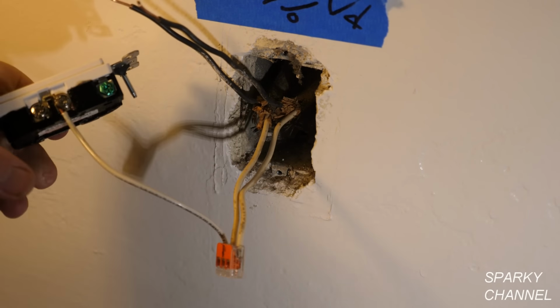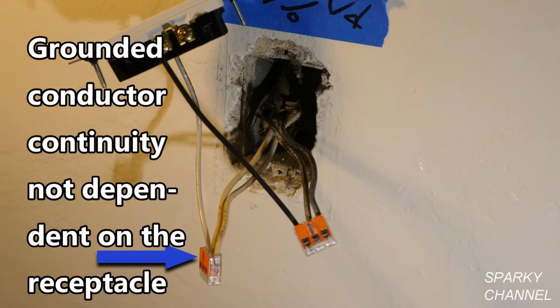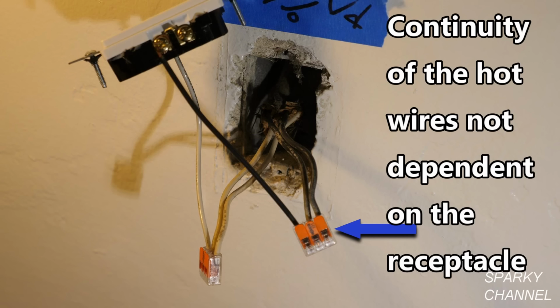Okay, so then I'm going to take the black hot conductor, prepare a pigtail, put that right in there, and I'm going to take that and go around either one of these terminals. It doesn't matter, they're hooked together. Tighten it down securely. Here you can see that the continuity of the neutral wires does not depend on the receptacle. If mechanical damage were to occur to the receptacle, electricity would still flow through the neutral wires back to the main panel. And because I also pigtailed the hot wires, in the event of mechanical damage to the receptacle, electricity would still flow to the downstream receptacles on the circuit.